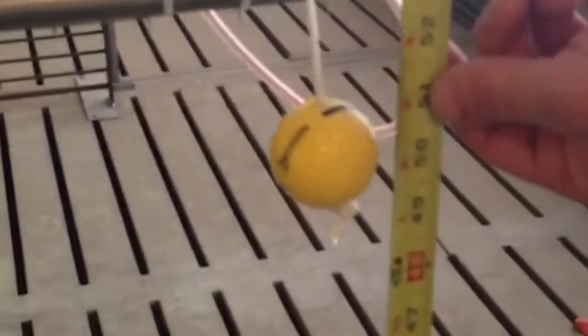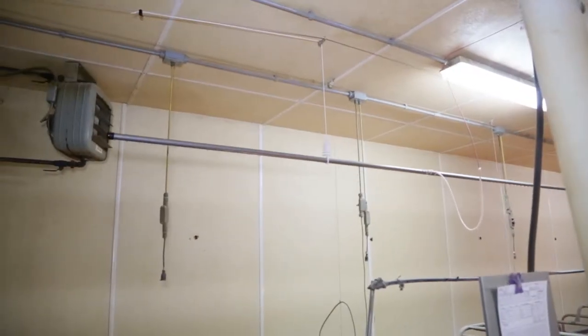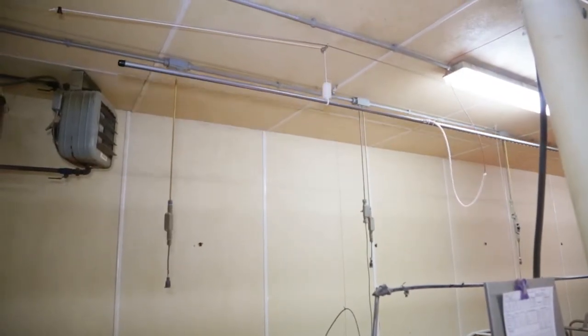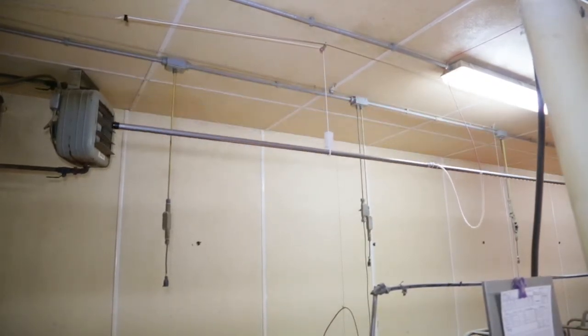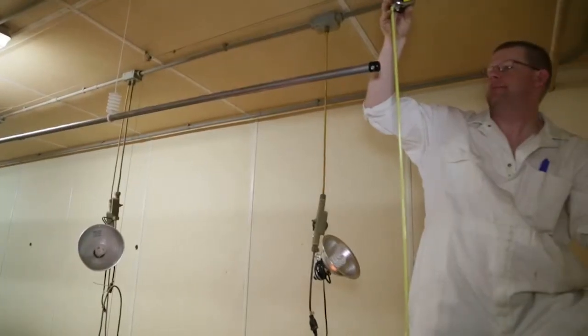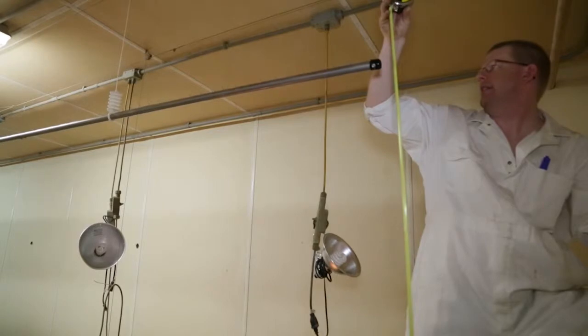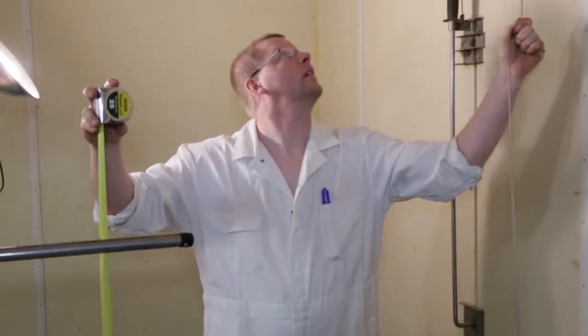During operation, the corona pipe should be just below the ball level. To gain maximum vertical clearance, if the corona pipe is pulled all of the way up to the ceiling, make sure the pipe insulators are not touching the pulleys. This will prevent damage during use. When all of the pipe insulators are touching the support pulleys, the corona pipe runs are adjusted to the maximum height, and each corona pipeline will move in unison with each other.